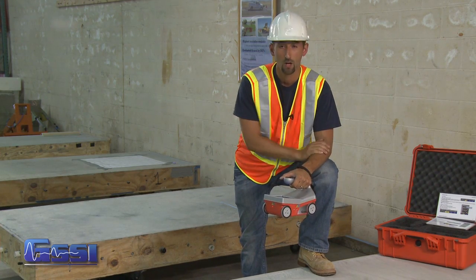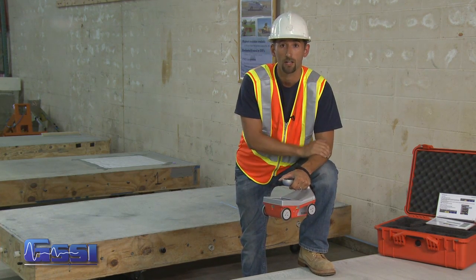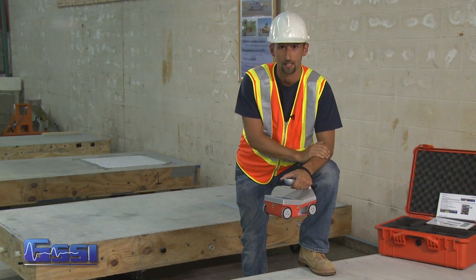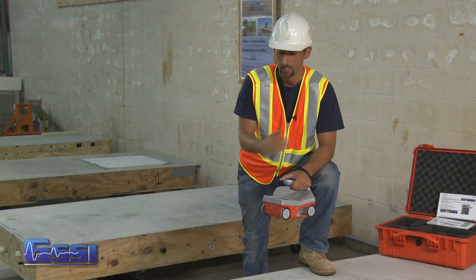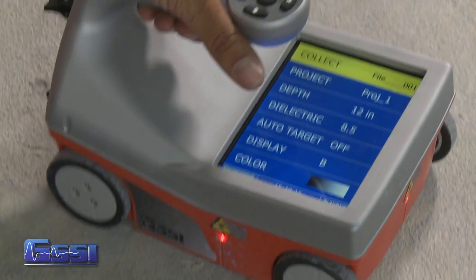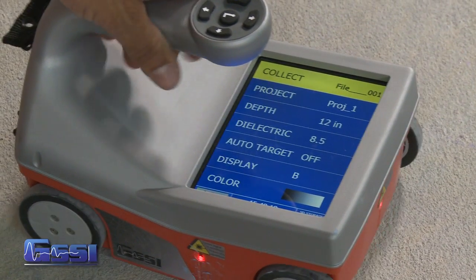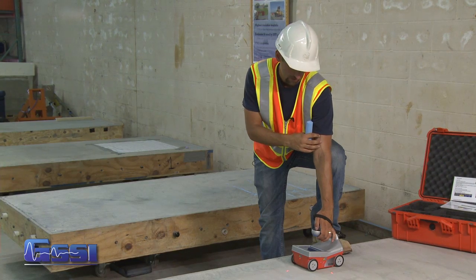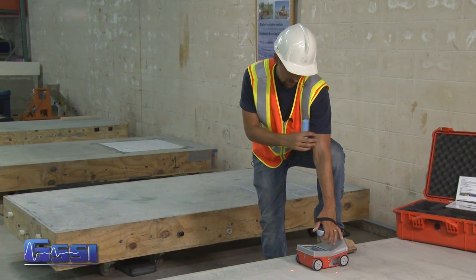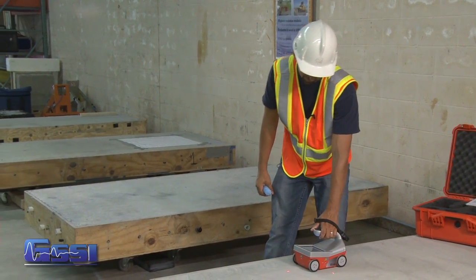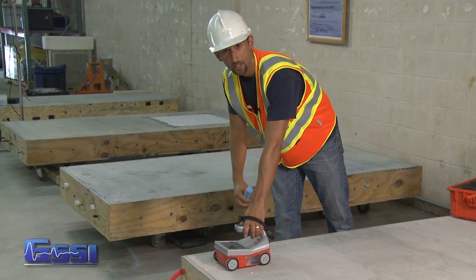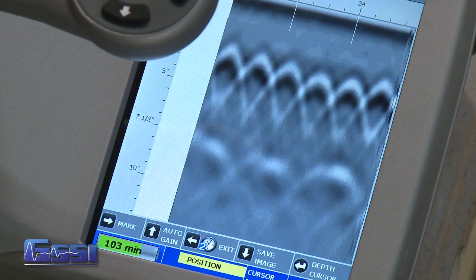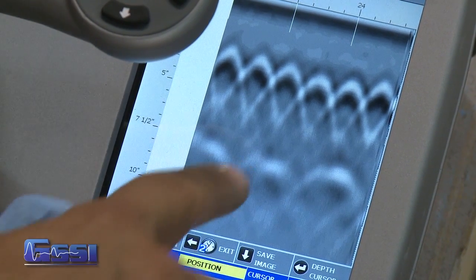What we're going to do is scan here and mark the tops of the pan decking, so you know where to drill without hitting any conduits in the valleys. I'm going to use the Structure Scan Mini in collect mode to collect some data. We'll push the system along and get a nice profile on the screen, then use the backup cursor to locate the targets.